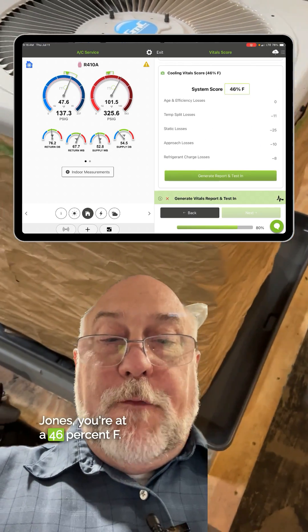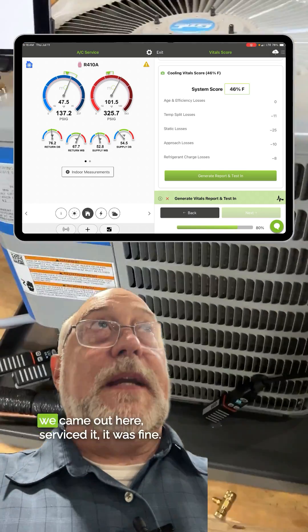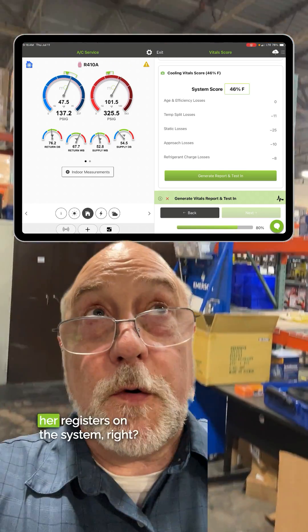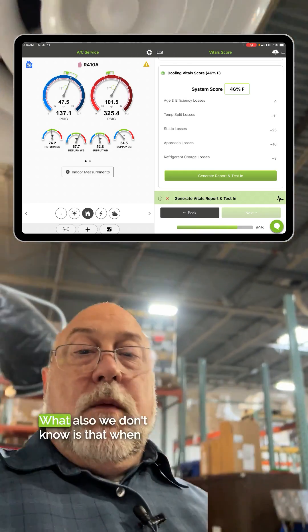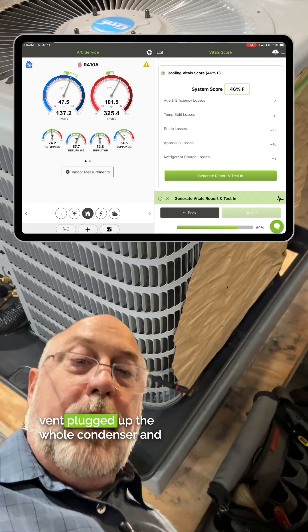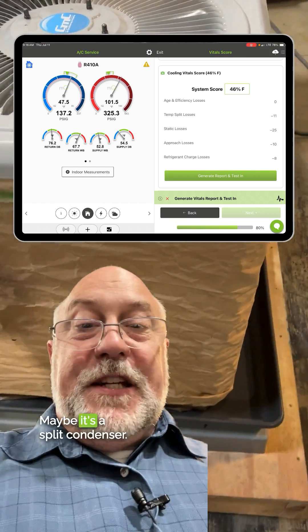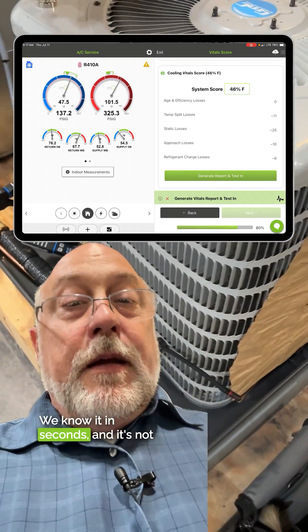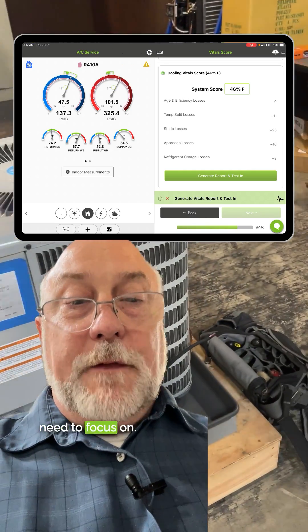And by the way, Mrs. Jones, you're at a 46 percent F. Now, what neither of us know is last year we came out here, serviced it, it was fine. This year Mrs. Jones has closed off three or four of her registers because her kids went to college — who the heck knows. What we also don't know is that when she washed all those clothes and the kids went to college, the dryer vent clogged up the whole condenser and it's full of debris. You may be able to see it, maybe not. Maybe it's a split condenser. We know. MeasureQuick knows. We know it in seconds. It's not about figuring it out — it's about figuring it out quickly. It's productivity, and that's what we need to focus on.